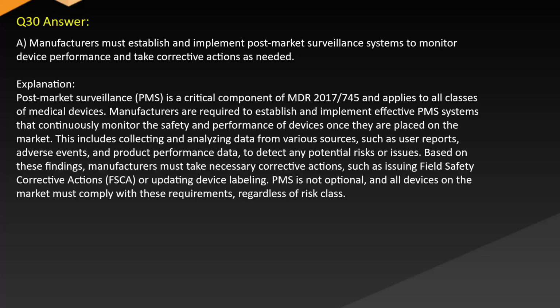Answer: A. Manufacturers must establish and implement post-market surveillance systems to monitor device performance and take corrective actions as needed. Explanation: post-market surveillance (PMS) is a critical component of MDR 2017-745 and applies to all classes of medical devices. Manufacturers are required to establish and implement effective PMS systems that continuously monitor the safety and performance of devices once they are placed on the market.